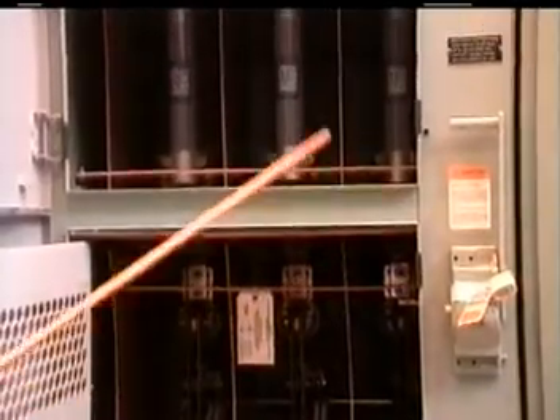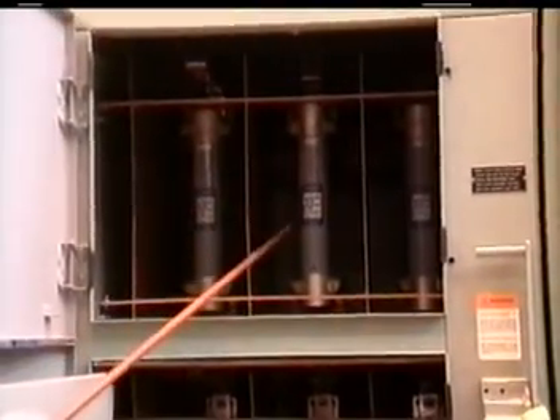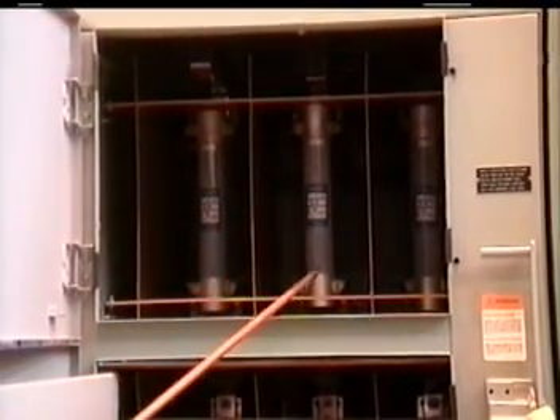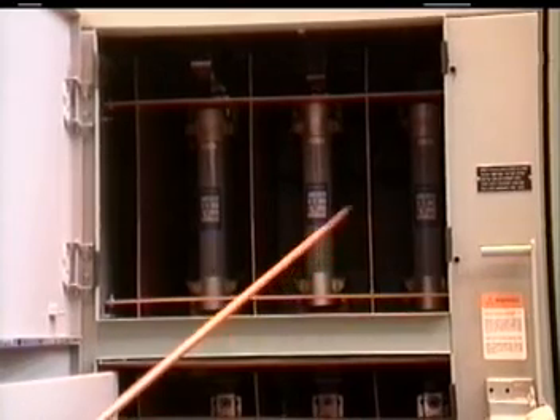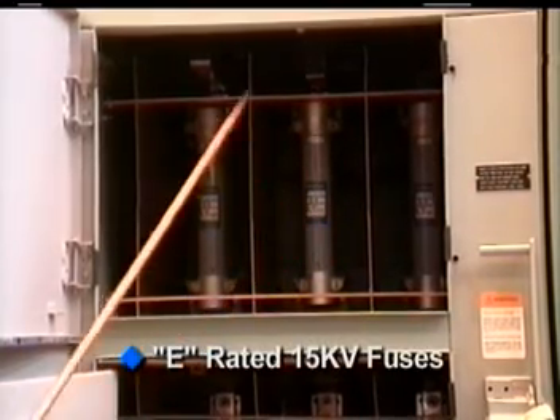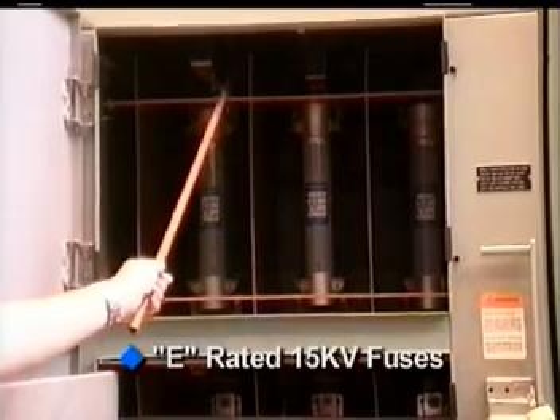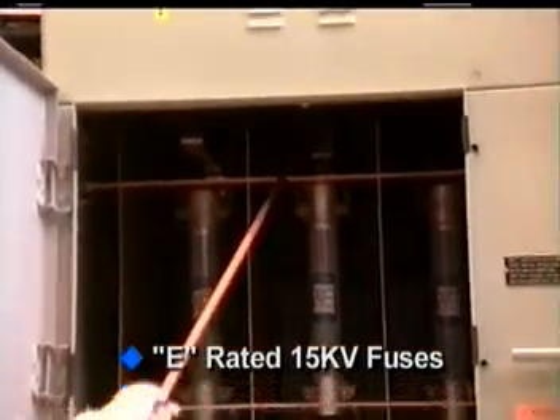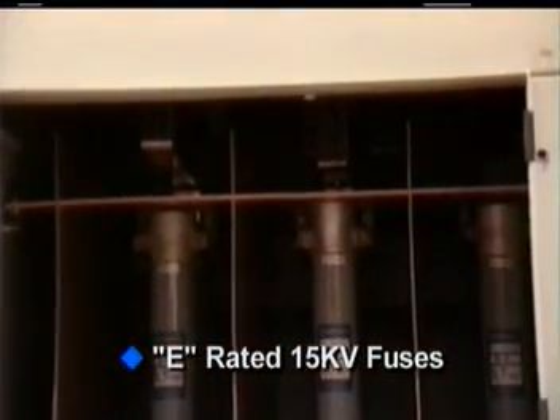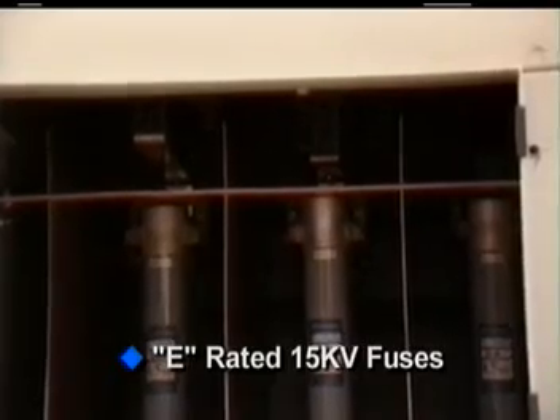The disconnect section also contains the E-rated fuses to provide for short circuit protection for the motor as well as the starter. In the top section of the disconnect section are also surge arresters, which provide for up to 60 kV of BIL protection for the system.